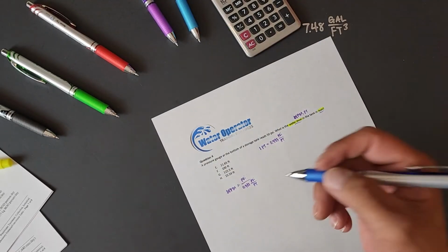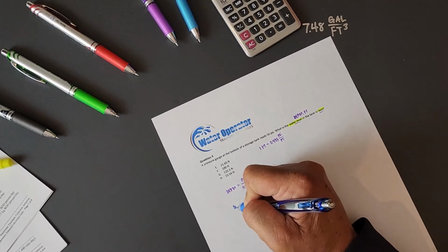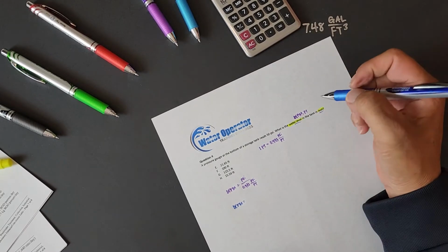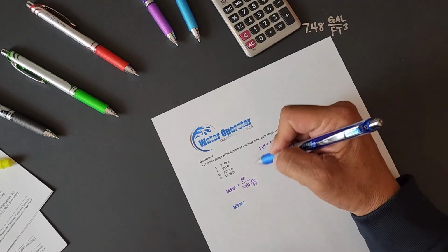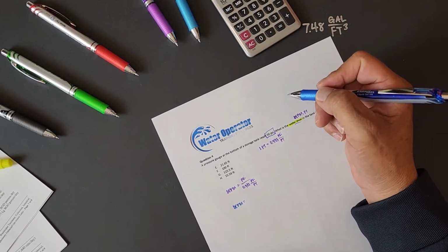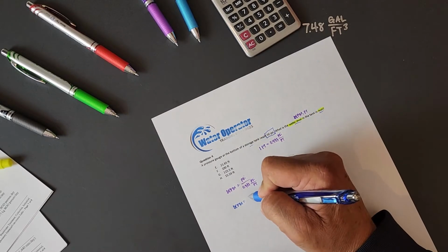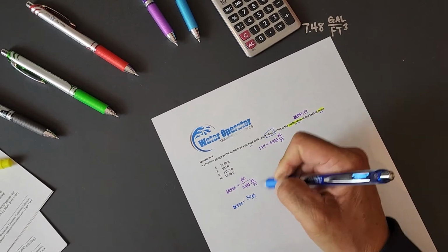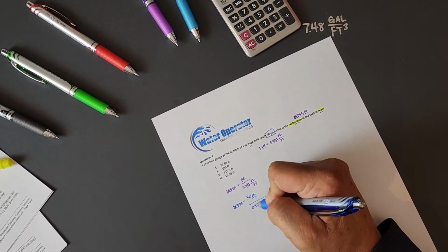Let's write this formula down and we'll stick in this information from the question. Depth equals, now what's the pressure? The pressure is 50 psi. So this is a pressure gauge at the bottom of a ground storage tank. So we will put in 50 psi over 1.